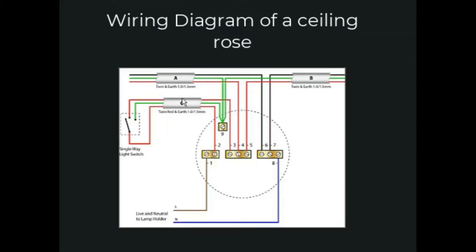The red cable going to terminal 3 is the live cable to the switch. When the switch is turned on, the current flows down the red wire to terminal 2. As the connector block is now live, the current will also flow down the brown wire onto terminal 1 and the light will come on.